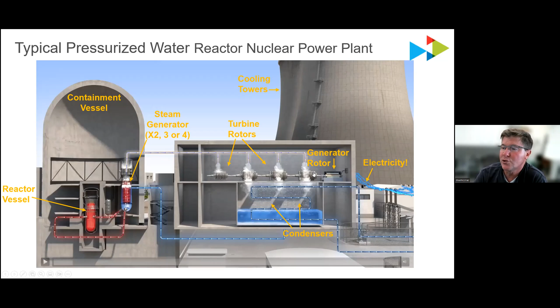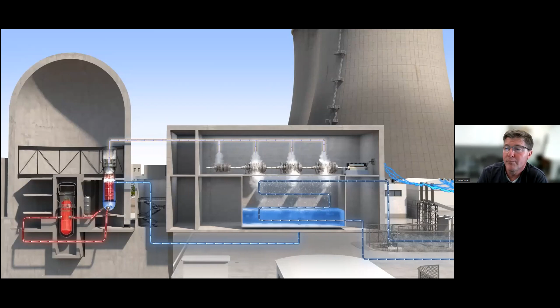And for all 4 of our Vogtle units, there'll be 1 high pressure turbine and 3 low pressure turbines spinning at 1800 RPM. Okay, so different plants have different designs, but for us, it's 1 high pressure, 3 low pressure turbine, all on 1 shaft, spinning a generator rotor at 1800 RPM. And then we use water from the cooling tower to condense that steam. Just like 1 pipe, there's literally thousands of tubes in 3 separate condensers underneath these 3 low pressure turbines. And that steam condenses the water in our condensers and gets pumped back in as a liquid. And then of course, the water from the cooling tower picks up the heat and it goes to our cooling towers about 120 degrees Fahrenheit. Different plants have different designs, but this is Vogtle 1, 2, 3, and 4, essentially pressurized water reactor.